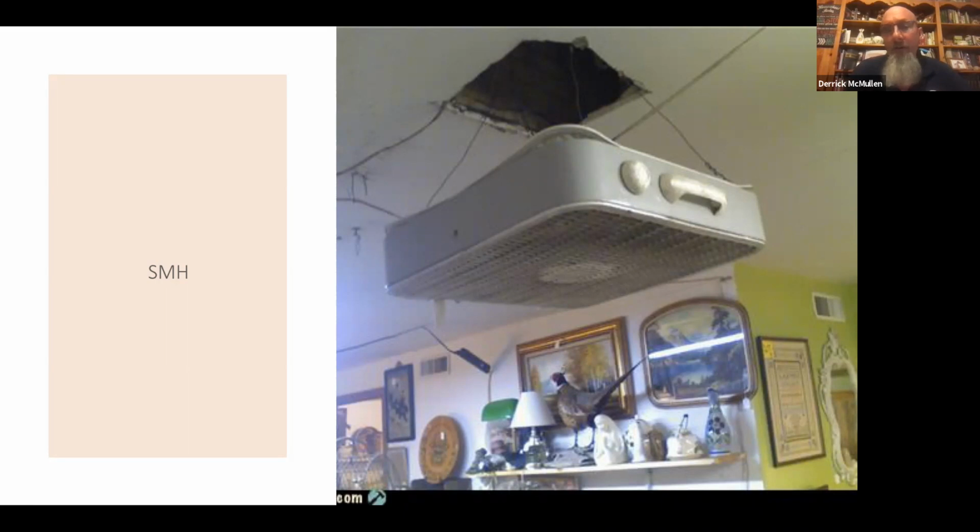And a lot of times, I'm sure everybody else finds it too, we find that it's been opened and closed several times, and the corner of the drywall will be busted off. So that is definitely an issue. That's an opening to the attic. So yes, the scuttle hole has to be minimum 1/2-inch drywall and tight fitting.